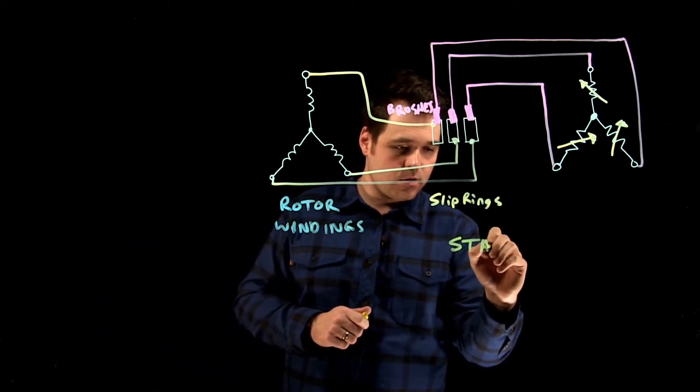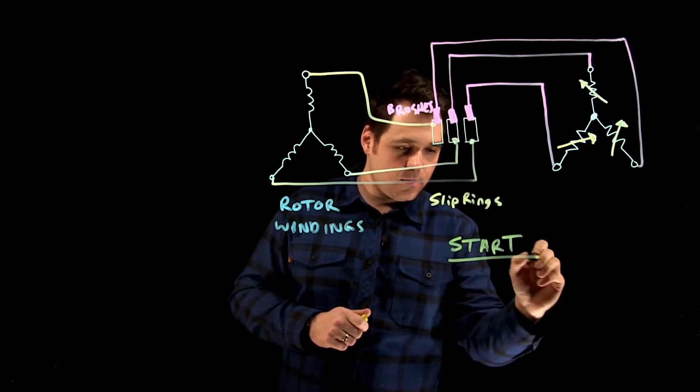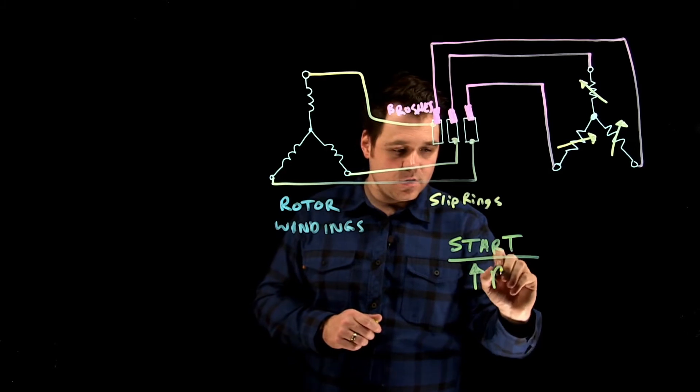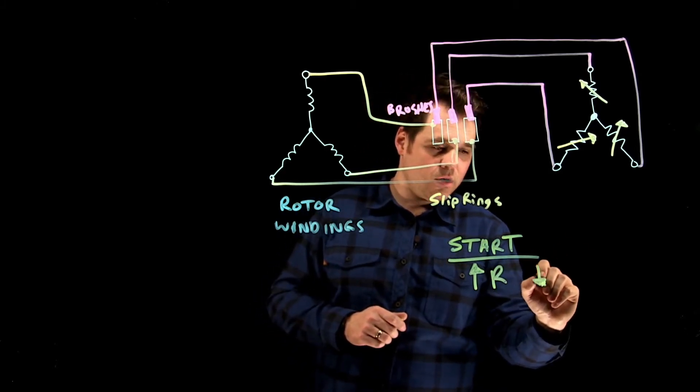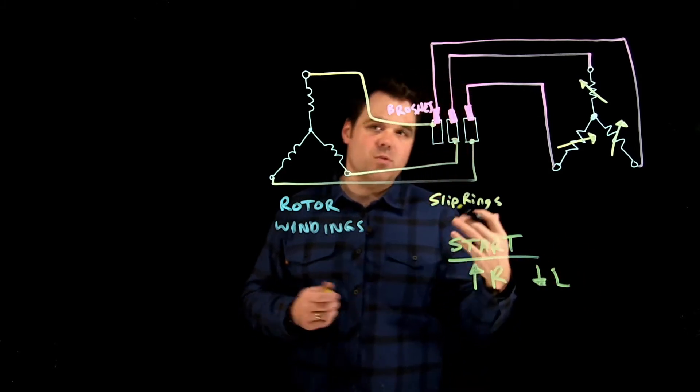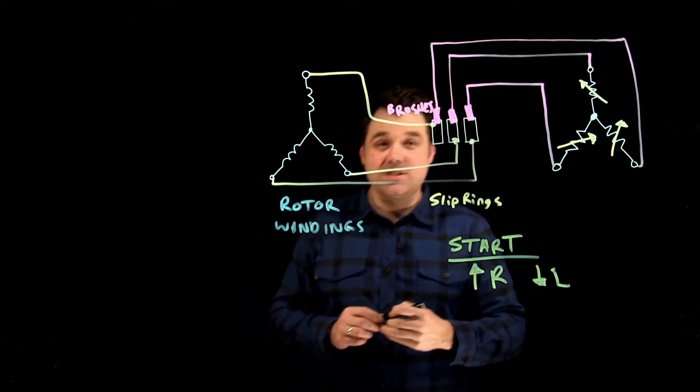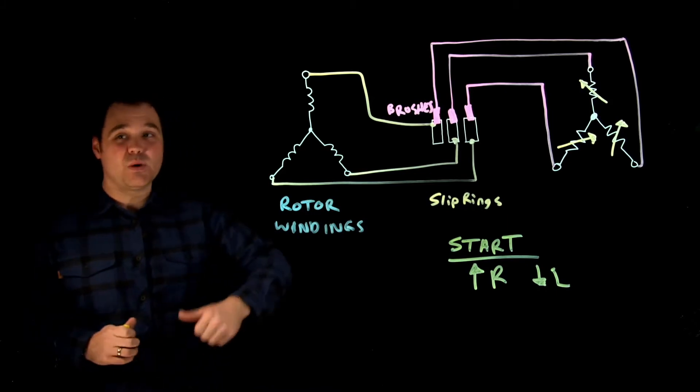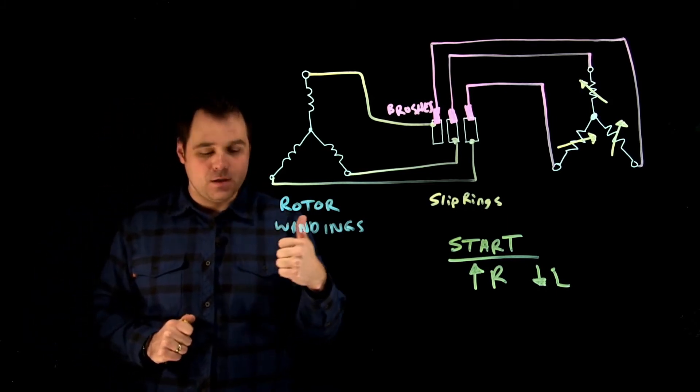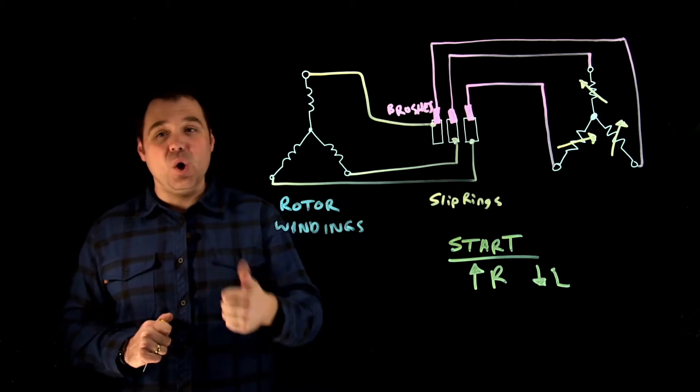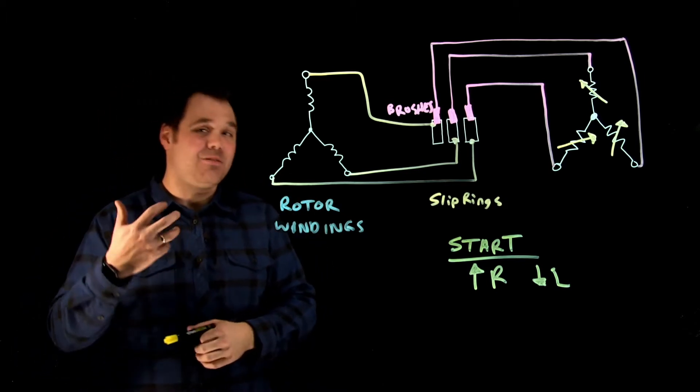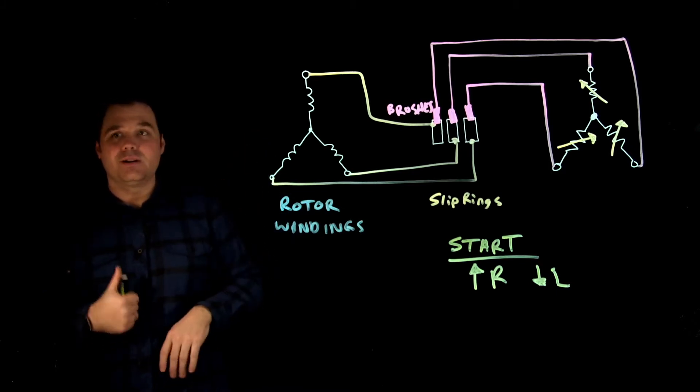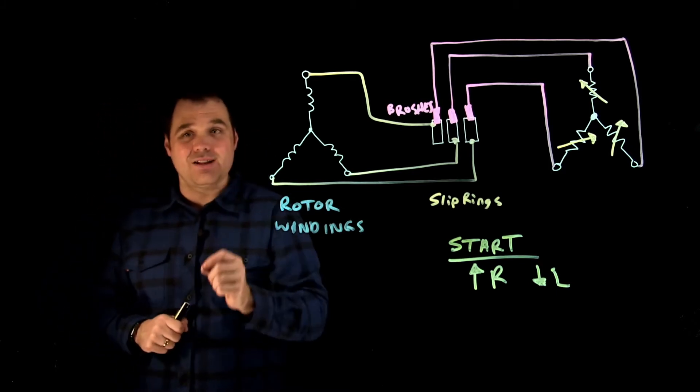And this is really important. So at start, I'm going to have a high resistance and a low inductance, or low x. So it's similar to a design D rotor. Now what that does is that gives me a really high starting torque, but a very low starting current. So I'm going to get you know, 275, 300% of my starting torque, and a low starting current, so a low inrush current, that's awesome.